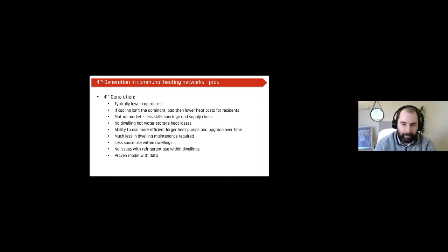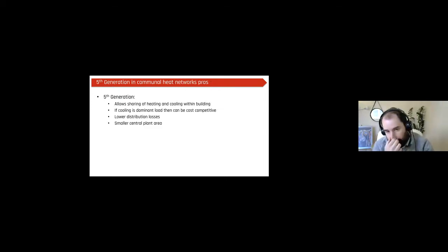Fifth generation in communal heat networks, the pros would be obviously that it allows sharing of heating and cooling within the building. So if cooling is a dominant load within the building, if it's a mixed use scheme and you have a high cooling load, then it can be cost competitive. You have lower distribution losses around the network, and it'll tend to have a smaller central plant area because you're shifting some of the heat generation into each individual dwelling.